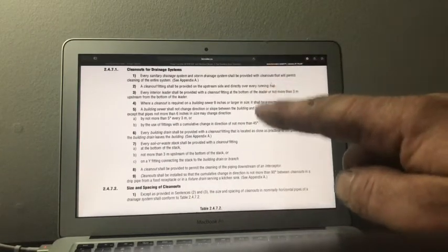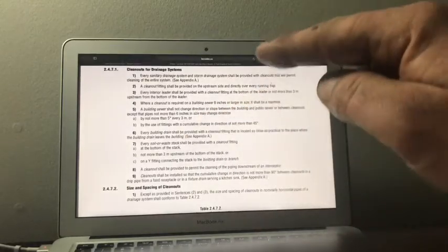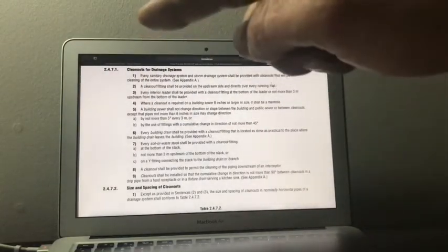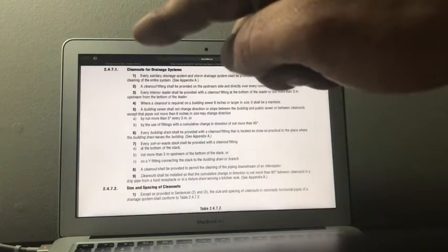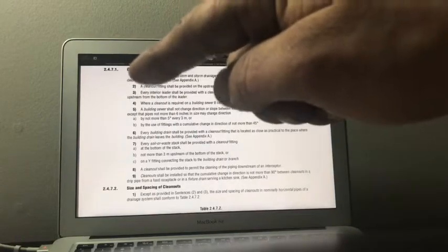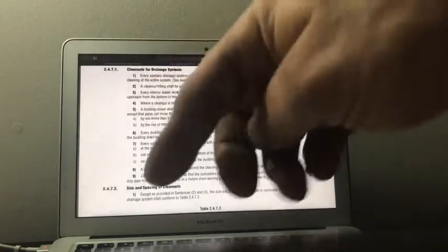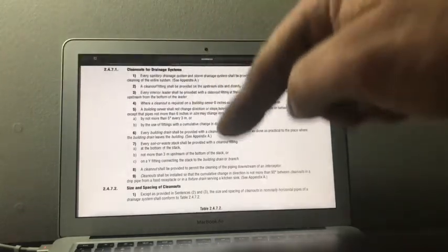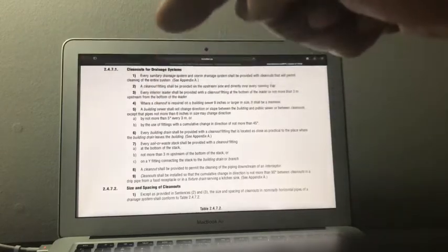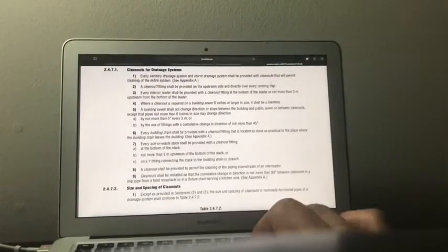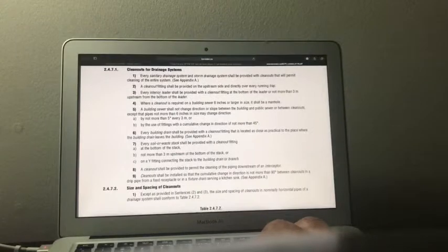So you have a P trap here. Sanitary T, clean out, or you can even go clean out through the floor and then put it flush with floor level. Or if you're in a parkade, you would just put a cap on there. The person can climb the ladder, remove that cap, and then obviously you would mess off this way. So it would just be P trap, sanitary T, mess off, and clean out up top. Right on. Okay, so that would be that.